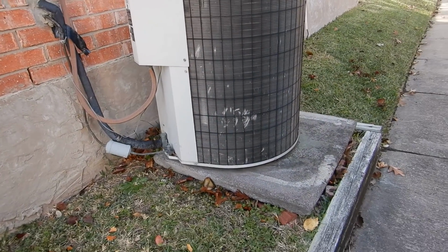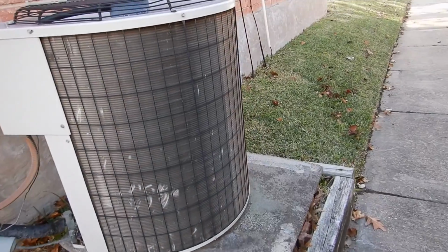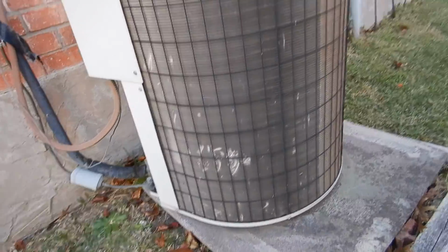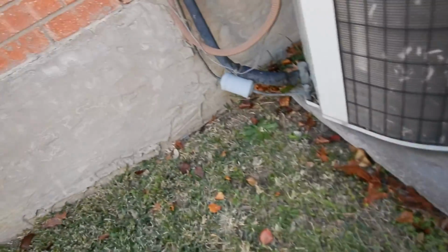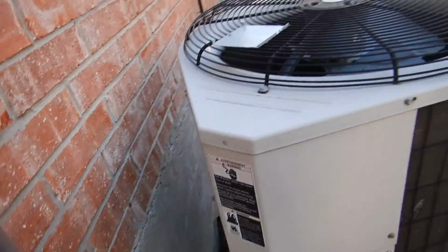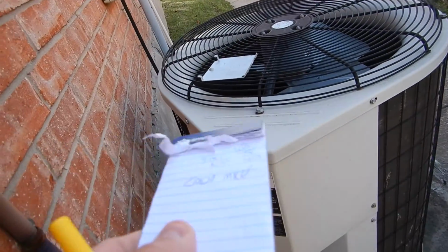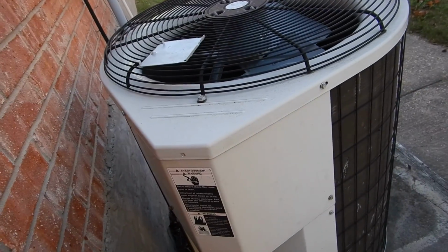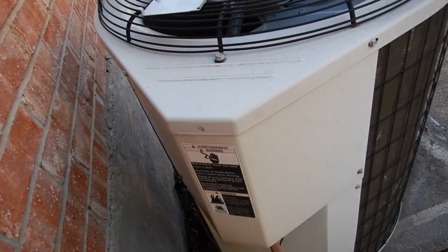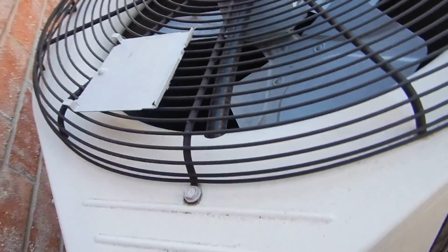So that's something to keep in mind. This is an R22 system. The system is 19 years old. About any technician is going to encourage you. The manufacturer specifies about 12 inches of distance between the condensing units and the walls. There's a little bit of leeway, I suppose, because it's a circular system instead of one of those blocks. But when you put a block system in, you need to be aware of that.